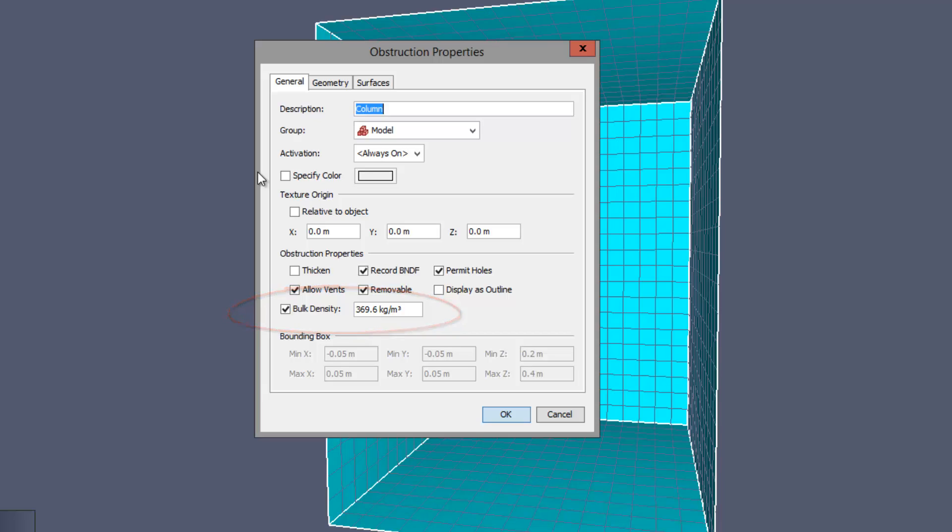This is an important option that says FDS should calculate the available fuel mass based on the volume of the obstruction and the bulk density, not the surface thickness.